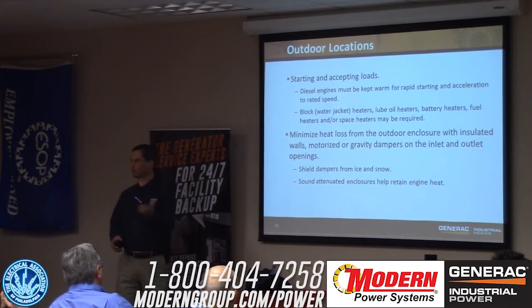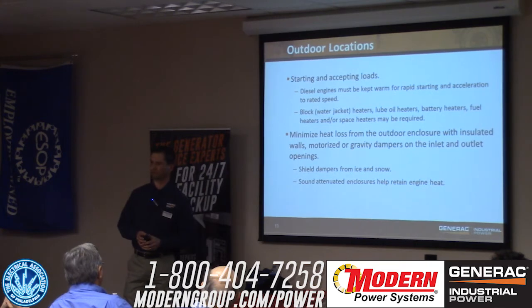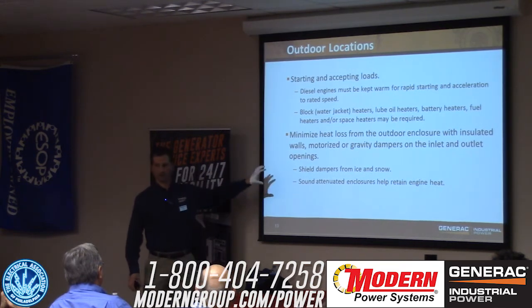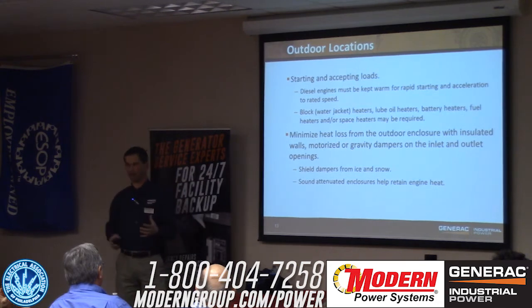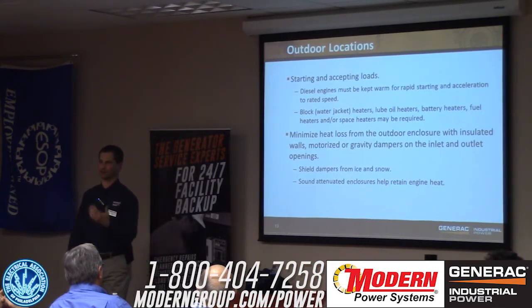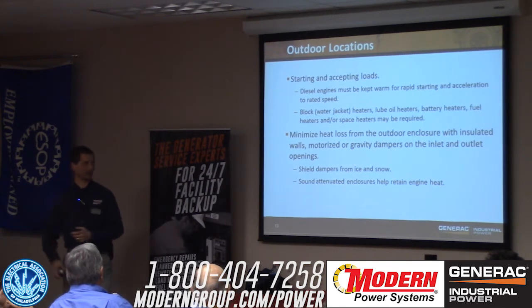Let's say you have no requirement for sound attenuation, and nobody cares how noisy the gen set is—there are places where it doesn't matter. You might still think about using a level 1 sound attenuated enclosure, because you get insulation in there that has thermal benefits too, and it can cut down on electric heat cost over the life of that gen set.